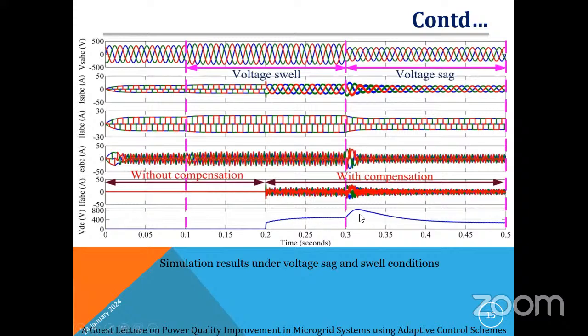So here you can see, suddenly at 0.3 second I have reduced the voltage levels from normal voltage to a low magnitude for checking the voltage sag condition also. See here, it is maintained less than 375, because the voltage magnitude is less than 375. That is the reason the controller is calculated based on the grid voltage variation.